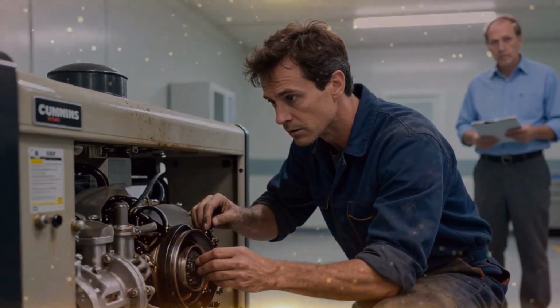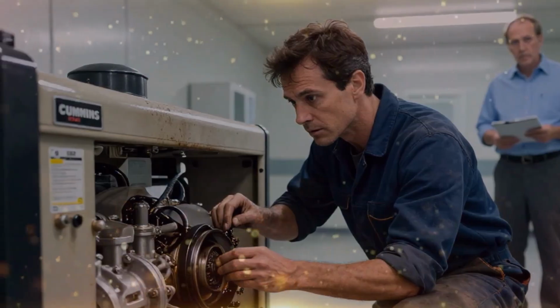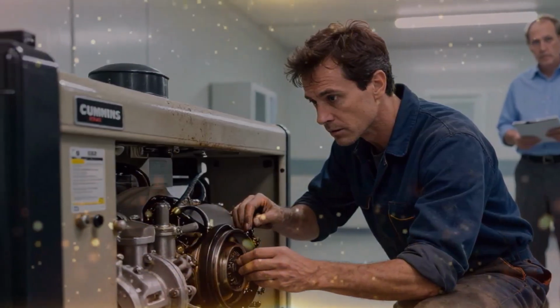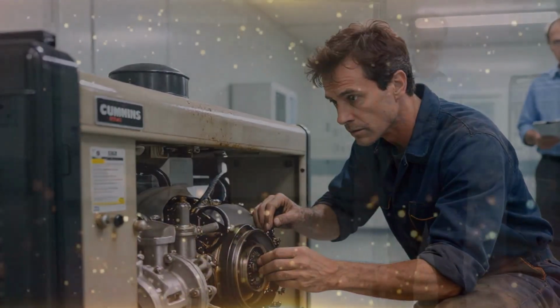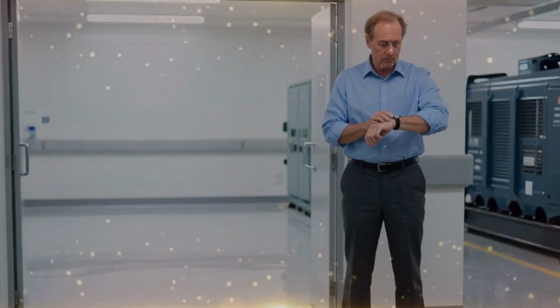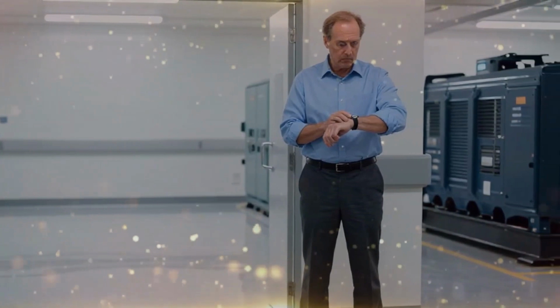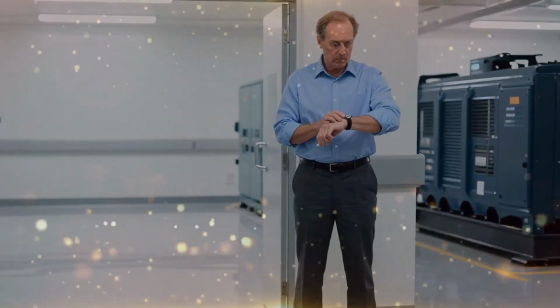"They make the voltage jagged. The governor tries to chase those jags. It has to oscillate the fuel rack hundreds of times a second to keep the frequency steady. When the valve tries to move that fast, those trapped air bubbles act like a spring."